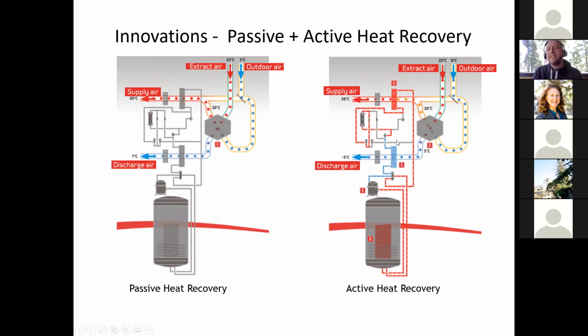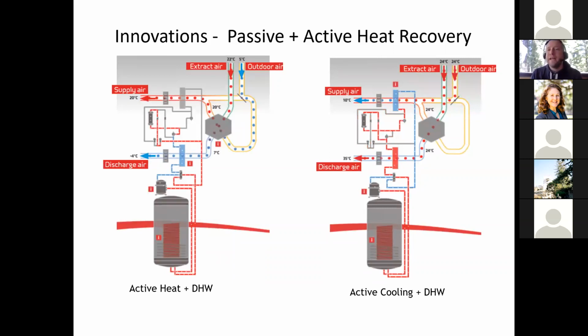The nice thing is, if you need warm air into your house, it can actually steal that air, and instead of heating your hot water at the same time, it can actually heat the incoming supply air. So it can provide some space heating to your room. It can either do that, or it can reverse and actually provide you with air conditioning, cool air into your room. And by air conditioning your room, at the same time, it can use that heat that it's stealing from the ventilation air to actually heat your domestic hot water.